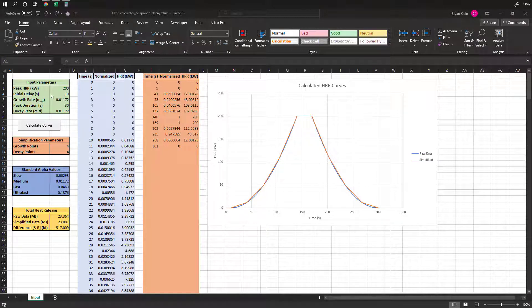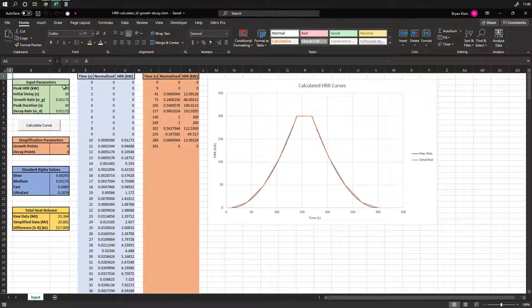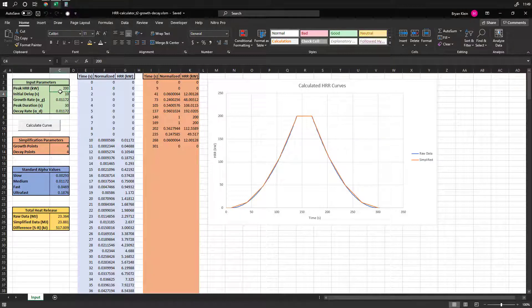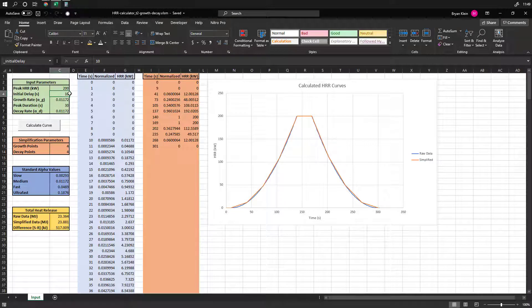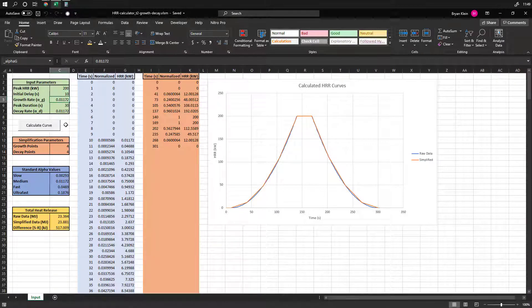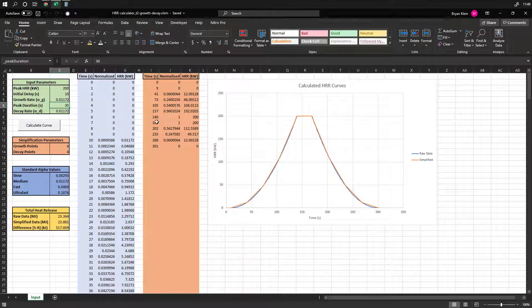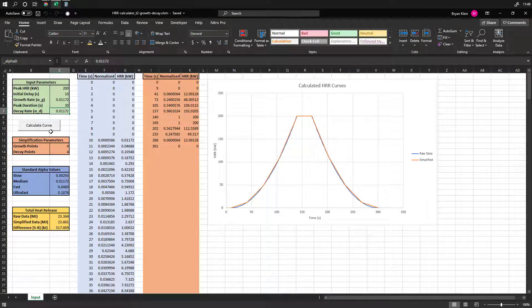There's a few input parameters. We have the peak heat release rate that you're interested in. If there's an initial delay, this could be zero if you want to, it'll still work, but how many seconds before the growth starts, and then your growth rate, your peak duration, so how long does it stay at peak, and then the decay rate or the rate on this decay side of the phase.